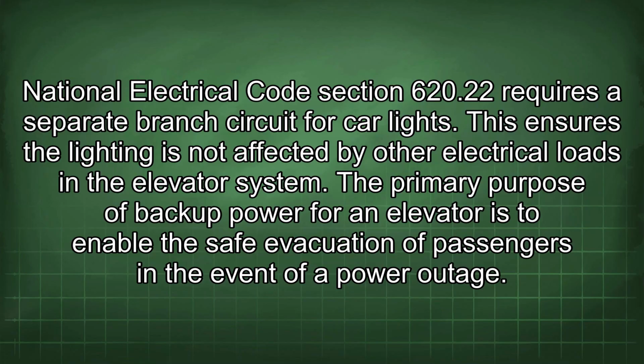National Electrical Code Section 620.22 requires a separate branch circuit for car lights. This ensures the lighting is not affected by other electrical loads in the elevator system.